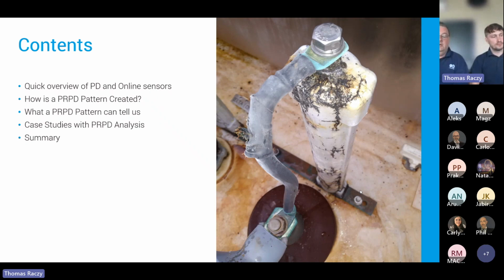So, quick overview, partial discharge. We hope that everyone attending this webinar has a good awareness of it, otherwise I don't think you'd actually be attending. Partial discharge over the years has been recognised as one of the most serious things that needs detecting on switchgear and cables and the like, in order to give us a heads up to do preventative maintenance rather than reacting like the fire brigade and having to work in reactive situations.